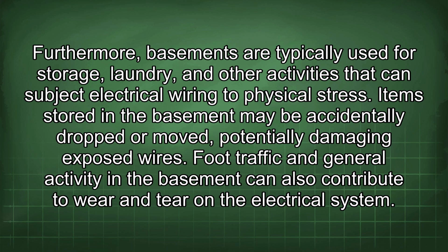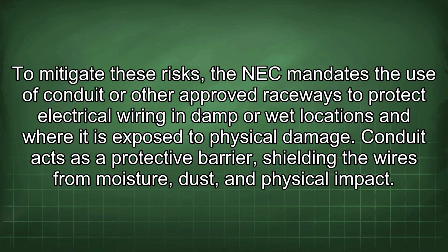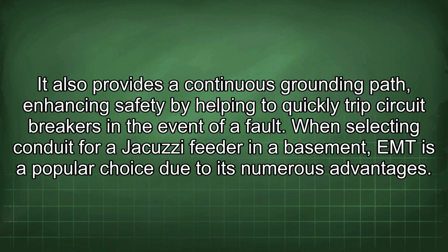Items stored in the basement may be accidentally dropped or moved, potentially damaging exposed wires. Foot traffic and general activity in the basement can also contribute to wear and tear on the electrical system. To mitigate these risks, the NEC mandates the use of conduit or other approved raceways to protect electrical wiring in damp or wet locations and where it is exposed to physical damage. Conduit acts as a protective barrier, shielding the wires from moisture, dust, and physical impact. It also provides a continuous grounding path, enhancing safety by helping to quickly trip circuit breakers in the event of a fault.